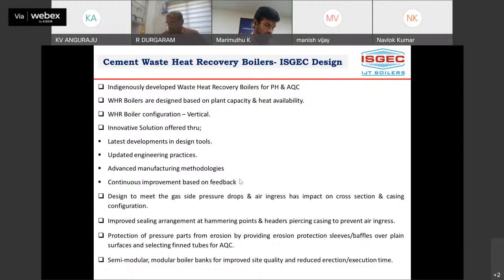Coming to erosion, baffling and material selection, yes, it's very much important in the AQC boiler, especially when compared with the PH. In general, we take care of the design side, whatever the pressure drops. Then coming to the air ingress issues, that we very much understand in all types of recovery boilers, specifically in cement plants, because we'll be handling a large volume of air with fans. I will be explaining what the things are when we go to the specific type of boiler.